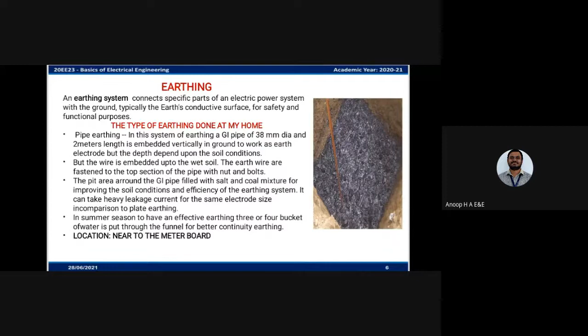The earth wire is fastened to the top of the section of the pipe with a nut and bolt. The pit area around the GI pipe is filled with a salt and coal mixture for improving the soil conditions and efficiency of the earthing system. It can take heavy leakage of current for the same electrode size in comparison to plate earthing. In summer seasons, to have an effective earthing, 3 or 4 buckets of water are put through the funnel for better continuity earthing. The location of the earthing pit is near the meter board.